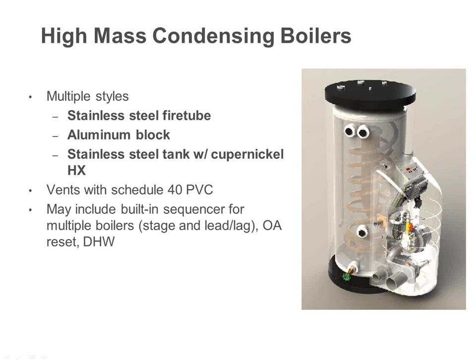Okay. There are different styles of it. Stainless steel fire tube. This one here has to be a stainless steel tank with a copper nickel heat exchanger. This manufacturer's actually been using this same design heat exchanger for probably 30 plus years for domestic hot water. The nice thing about this unit is it does have that capability of dealing with very, very small zones. It also has the capability of dealing with a lot of dirt. There's actually about 3 to 4 inches of area underneath that heat exchanger of just blank space, basically. It's just holding water. That's all it is. So you can get a lot of crap in there before you even start touching the heat exchanger.